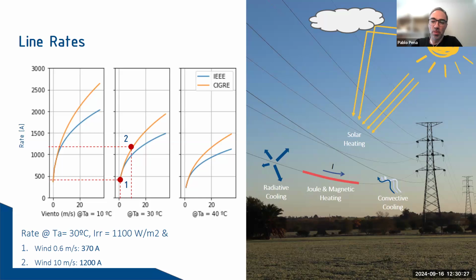However, the reality is that winter temperatures are often below 30 degrees. I refer to Celsius degrees. And irradiance is lower, especially at night, and wind speeds are usually higher than 0.6 meters per second. As a result, much of the time there is extra capacity that isn't being utilized. And this is what dynamic line rating seeks to capture. Wind is the most sensitive variable, so if instead of considering low wind, we use a wind speed of, for example, 10 meters per second, the line rate will increase by a factor of 3, as in the example.